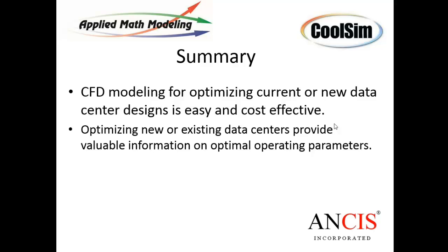Question here about modeling OptiCool systems unrelated to our webinar, rear door heat exchangers. Yes, we can model rear door heat exchangers, and that's not a problem. You treat them very much like you would an in-row cooling unit, but it's sitting behind instead of beside, and yeah, you can model those.